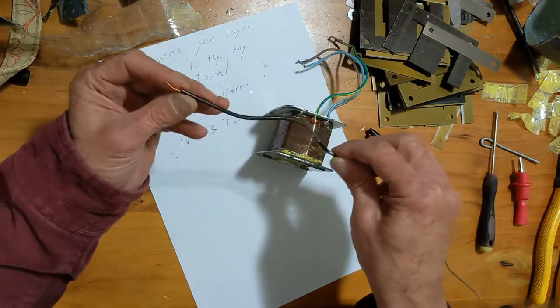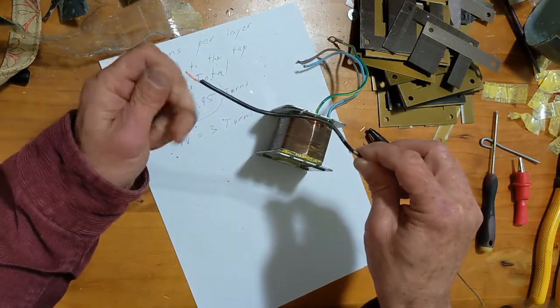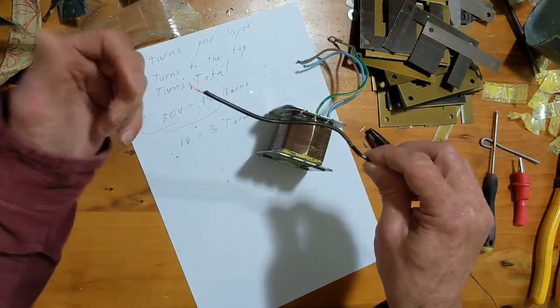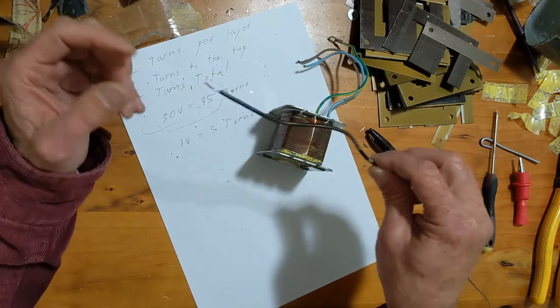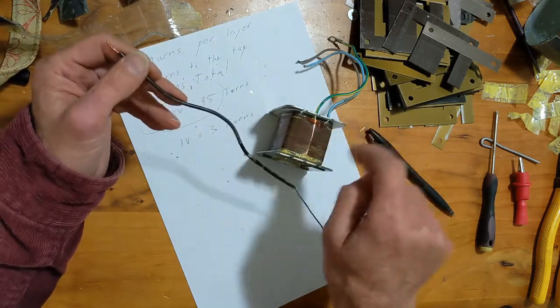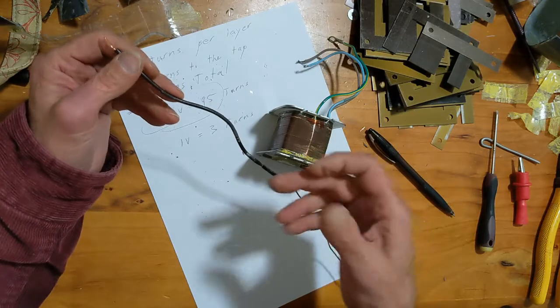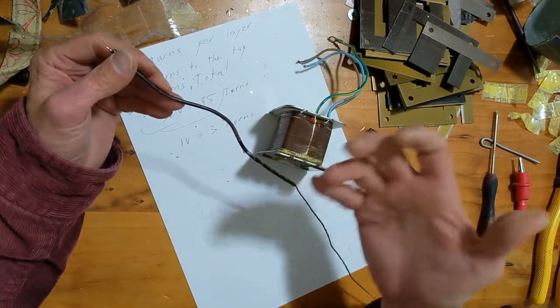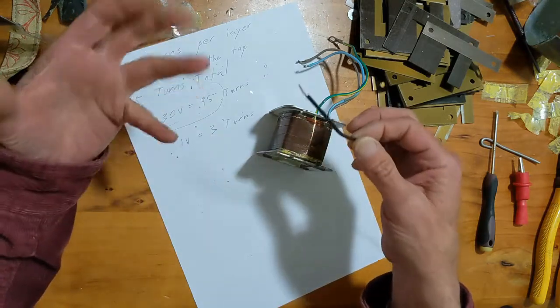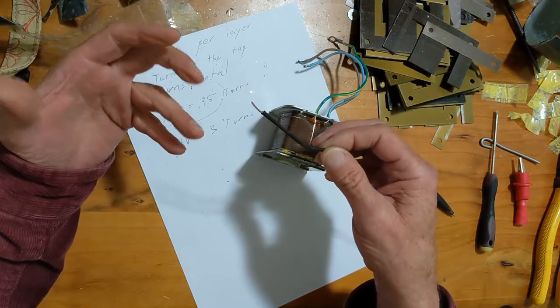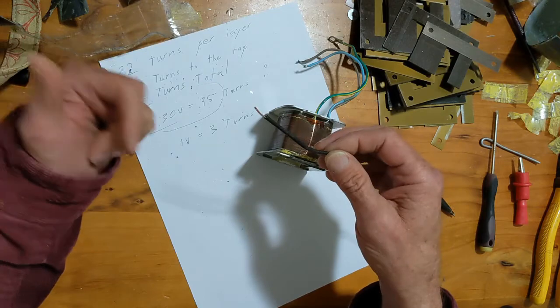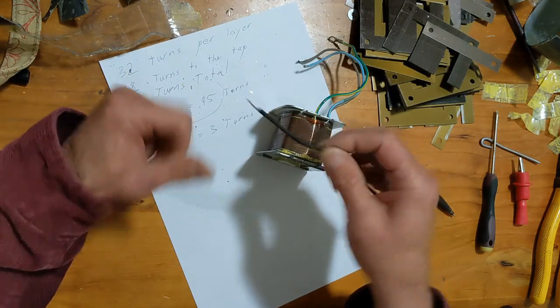Now you might think, looking at the size of the conductor on this secondary, that it's way overrated for 3 amps. But you've got to remember that all these turns are bound up together and the heat is going to build up inside the transformer. So the wire needs to be much larger to cope with that current when it's all bound up and the conductors are running in parallel with each other.